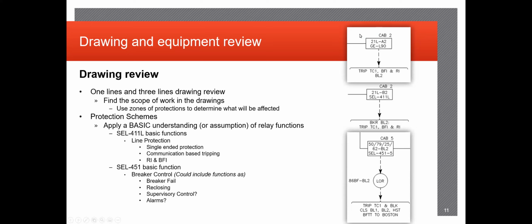And you can see in this example, it's been known for quite some time that the majority of the time clients specifically use SEL for primary and GE as backup. That's starting to get whitewashed, and we've been getting a lot of work involved upgrading GE relays to SEL, even as the backup relays, just because I believe they're more user friendly in the field, and I think a lot easier to troubleshoot if you do run into problems. But in this example here, you can identify that they have a GE L90 as their line protection for their backup, and their 411L for their primary, as well as the 451 for the breaker.